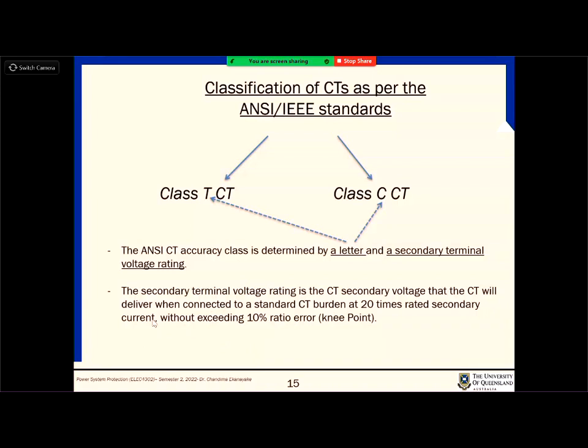The primary voltage is one thing, but the secondary voltage is also important, which is given for the operation of our devices, because we are working with relays. Relays can take a certain amount of voltage, so those secondary terminal voltage ratings are also given. What is the secondary terminal voltage? For a CT, usually we are dealing with current. When you have the rated primary current, you will have the rated secondary current. But the secondary terminal voltage means the voltage the CT delivers when connected to a standard CT burden at 20 times rated secondary current. Can you remember that 20 times thing?